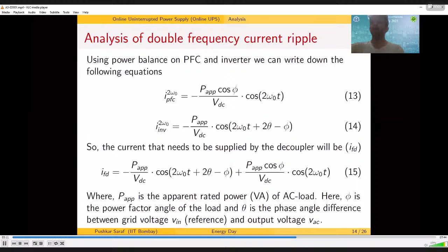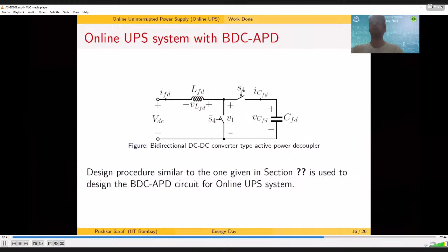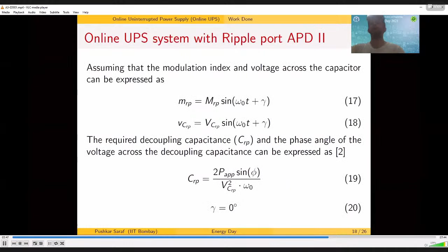After we minimize the double harmonic current using control based power decoupling, we can then use the active power decoupler to compensate for that current. We decided to look at two topologies for an online UPS system: one is the bidirectional DC to DC converter topology, and the other is the ripple port type topology. The ripple port type topology uses the following design equations.